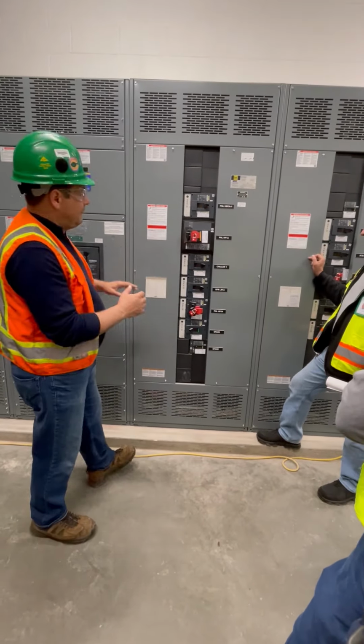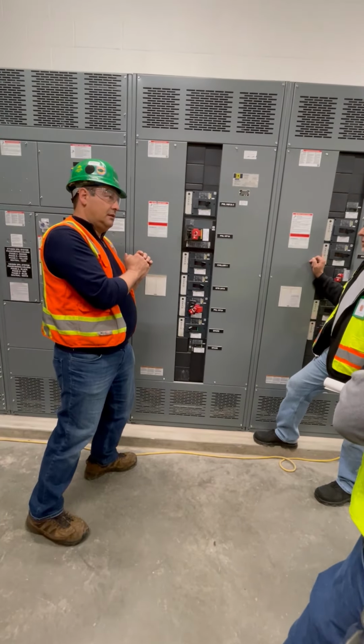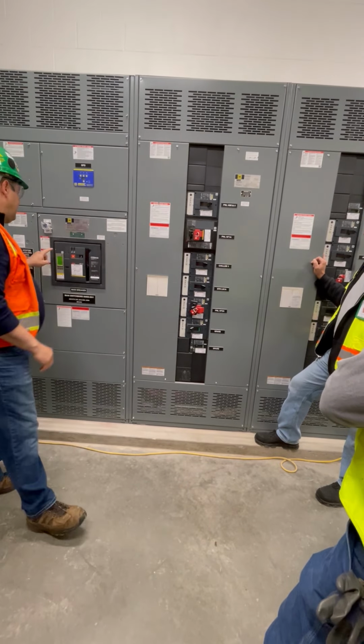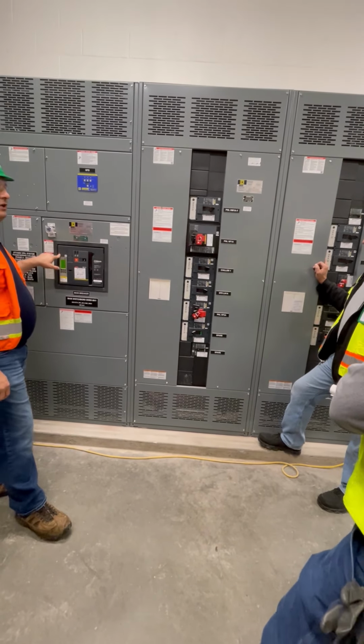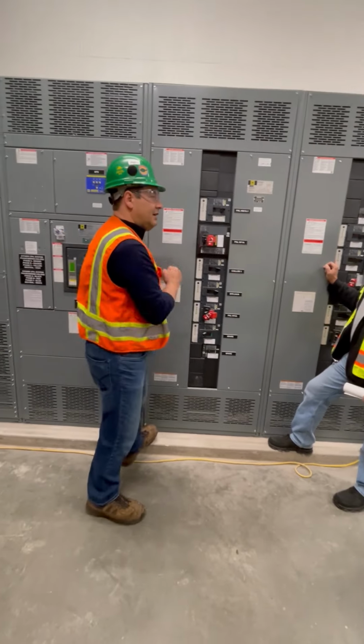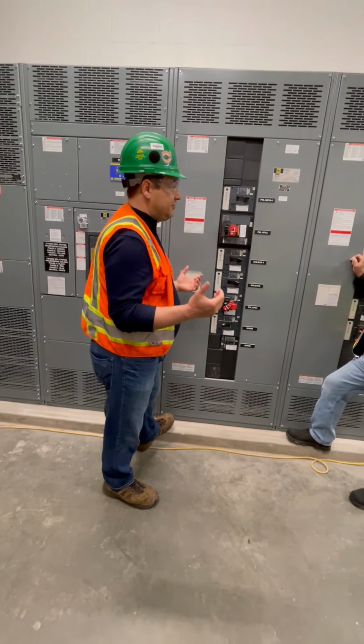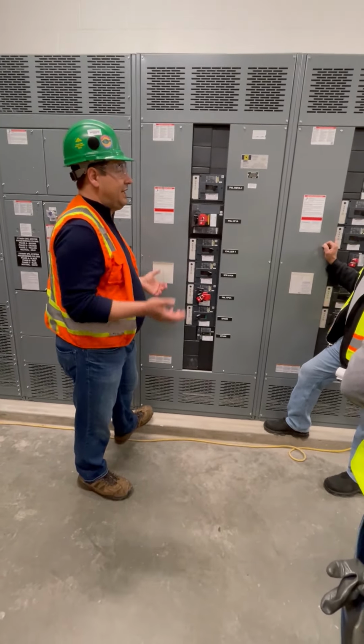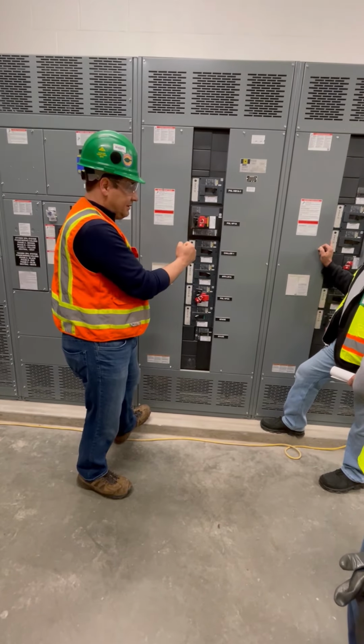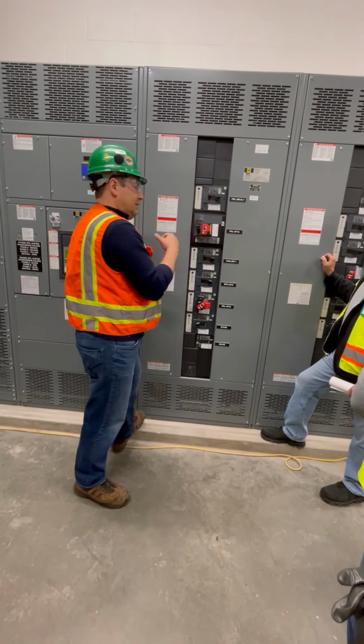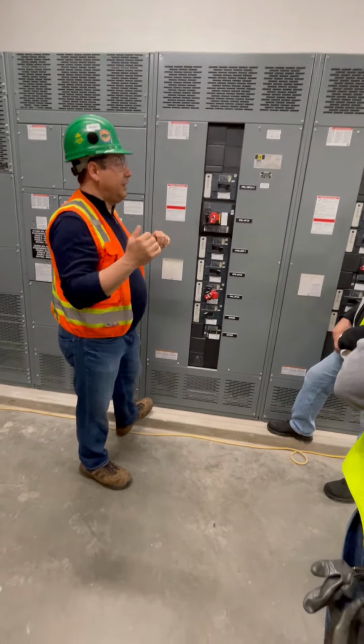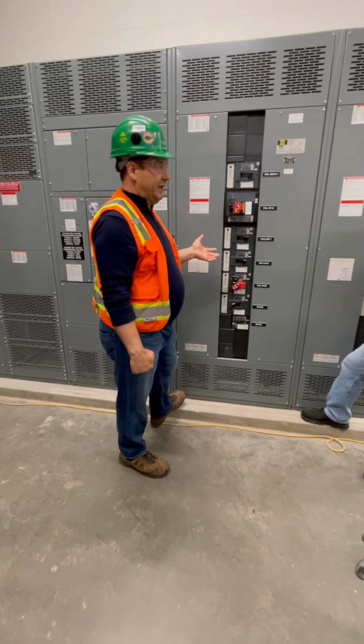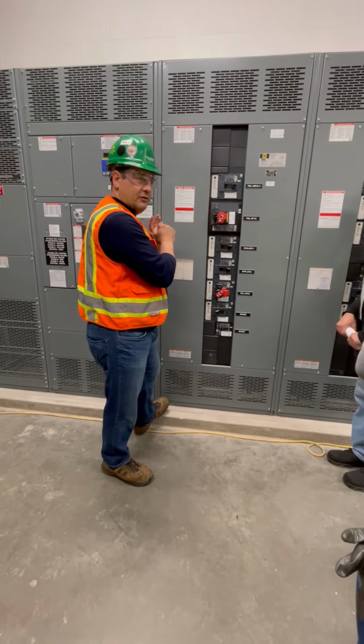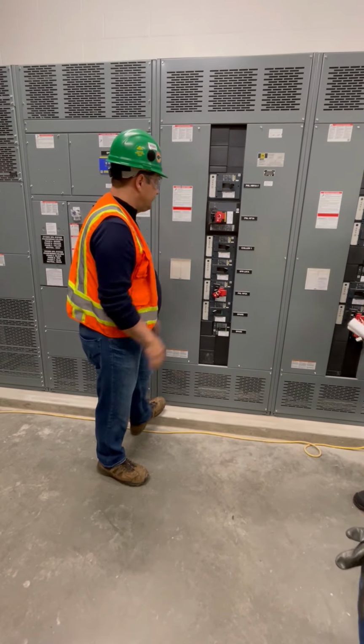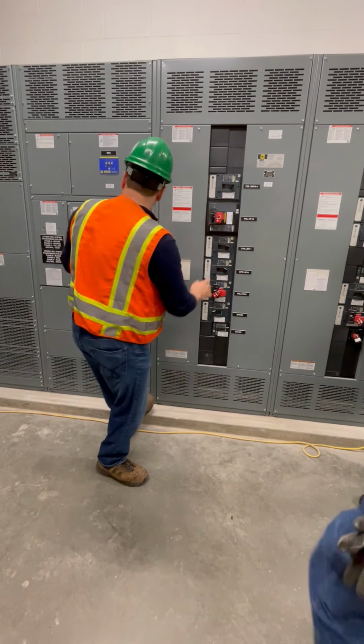Now, that resetting is almost the same concept as this red button over here. Because if you have to reset the breaker, that tells you that it tripped on something, right? It's not you operating the breaker on and off, it tripped on something. So having to reset is again part of the reason that makes you think, why did that breaker trip in the first place? And should I look at the system before I throw it back into a fault again? Just keep that in mind.